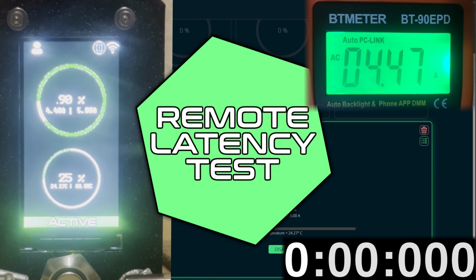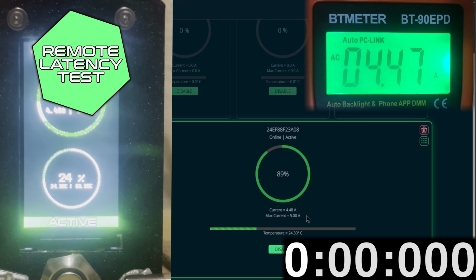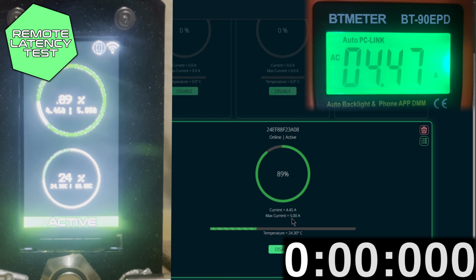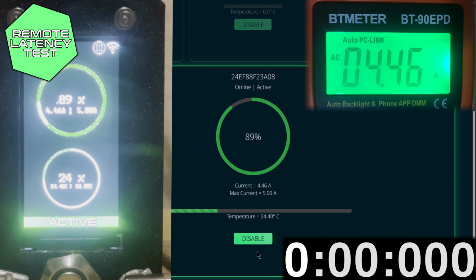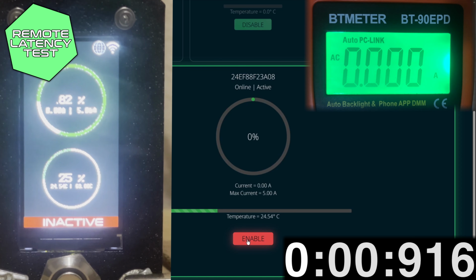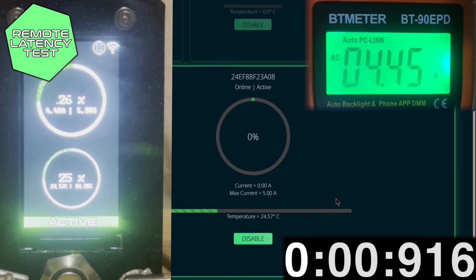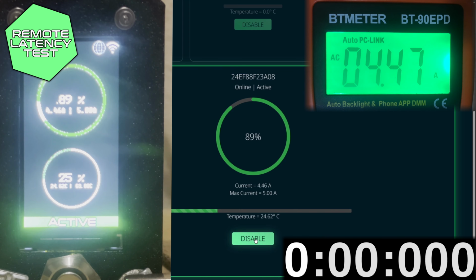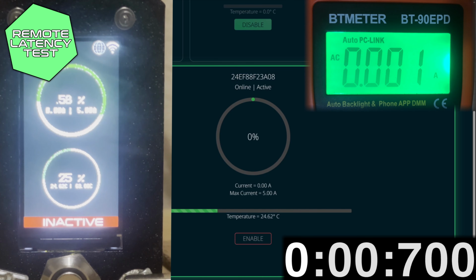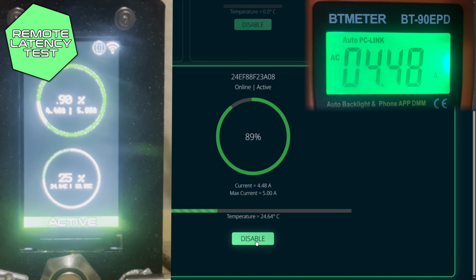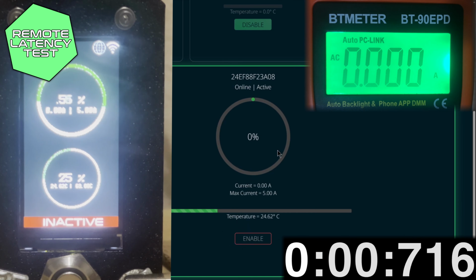And for the final test, we have the remote latency test. So on screen, we have the LCD display. We have the multimeter as just a basis of comparison. Remote dashboard right in the middle, and then just a timer to showcase the speed of the tripping. So I will go ahead and now trip the breaker remotely. And as you can see, in under a second, it goes from 4.5 amps down to 0. We'll go ahead and do it again here. This time about 700 milliseconds. And once again, about 716 milliseconds for the last attempt.